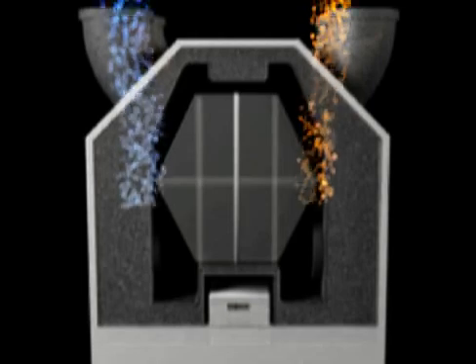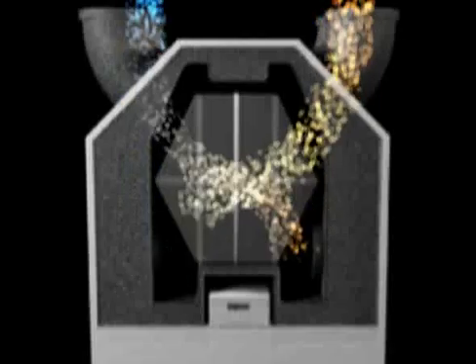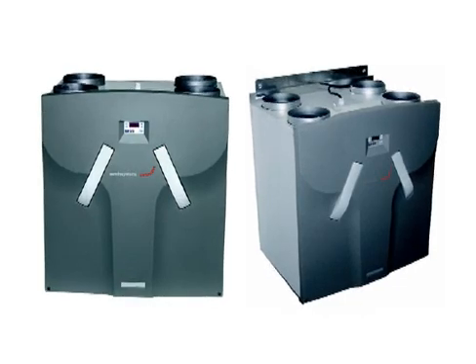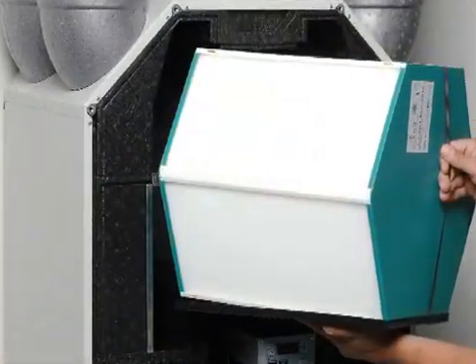The energy is then removed from the warm outgoing air in the heat exchanger of the ventilation device, where it's used to heat the cool fresh air. Servicing the ventilation device simply consists of regular replacement of the dust filters. The heat exchanger can be easily removed from the ventilation device and cleaned with water.